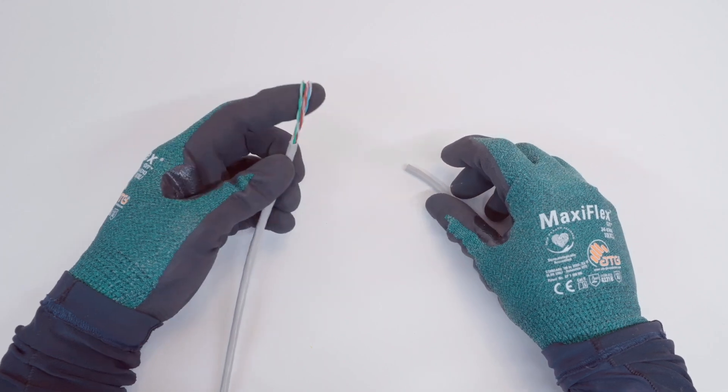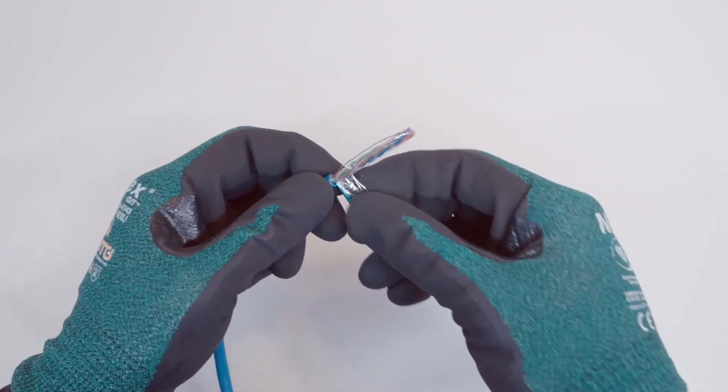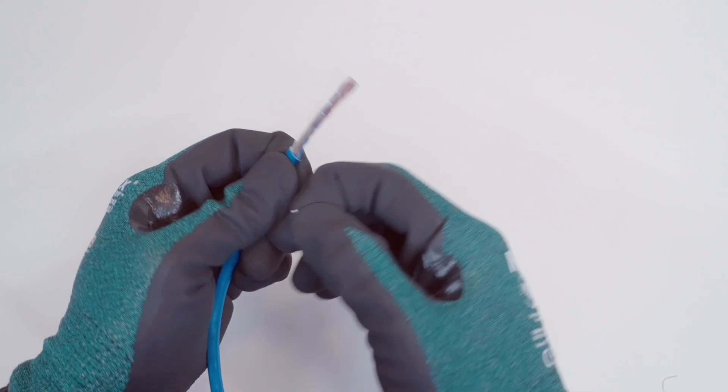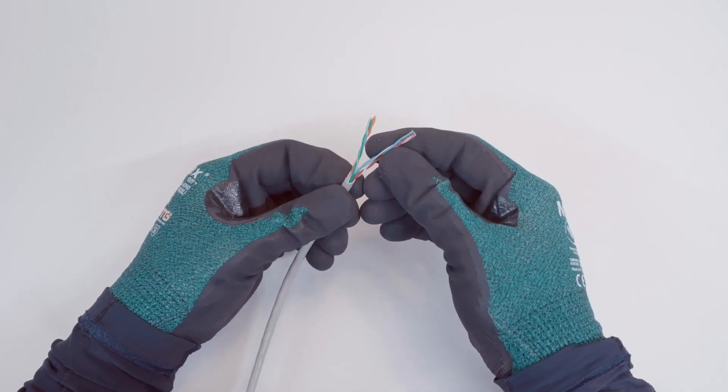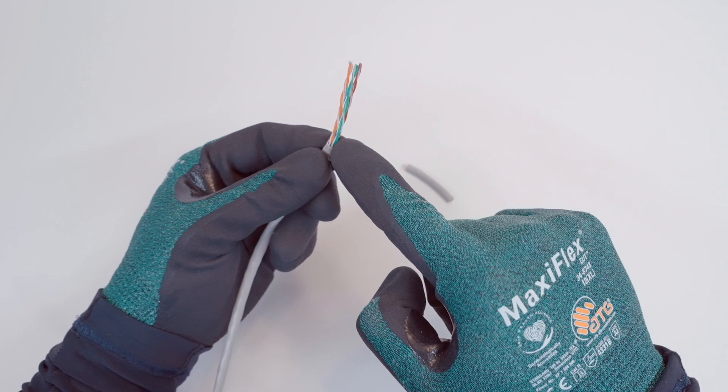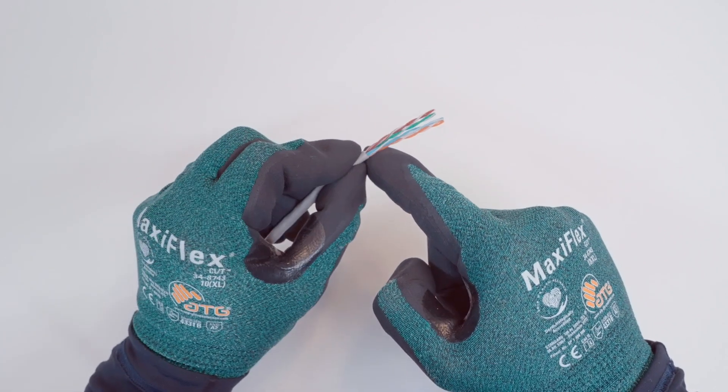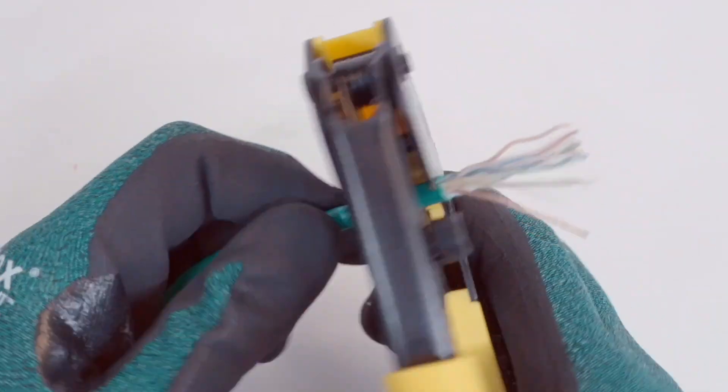If using shielded cable, unwind the metal shielding or foil from the wiring and cut it off. Inspect the wiring within the cable, especially at the end of the jacket, to ensure that it was not nicked or cut while removing the outer jacket. If any wires are damaged, cut the stripped end off and start over.